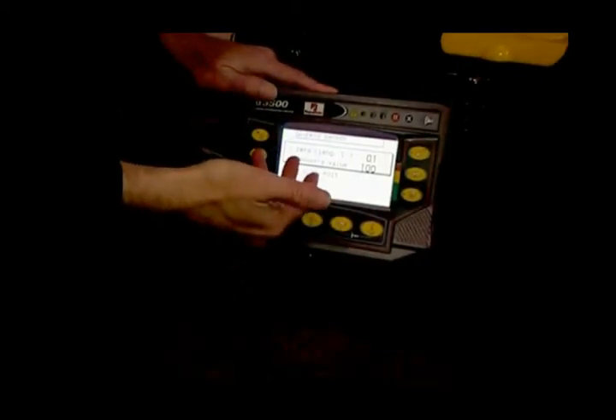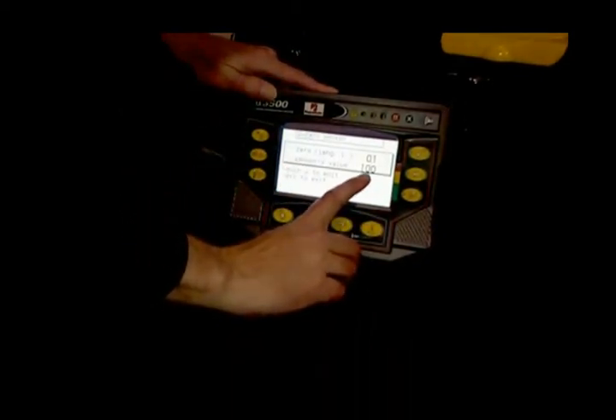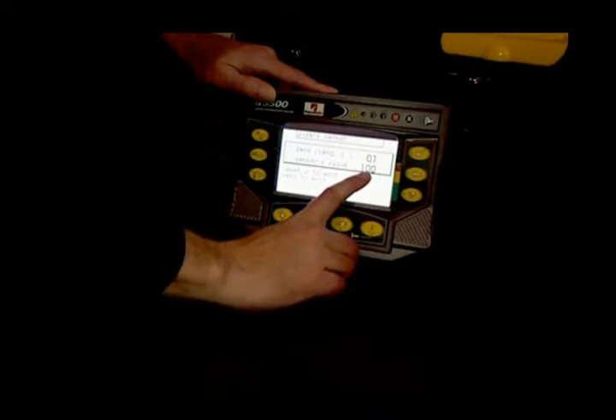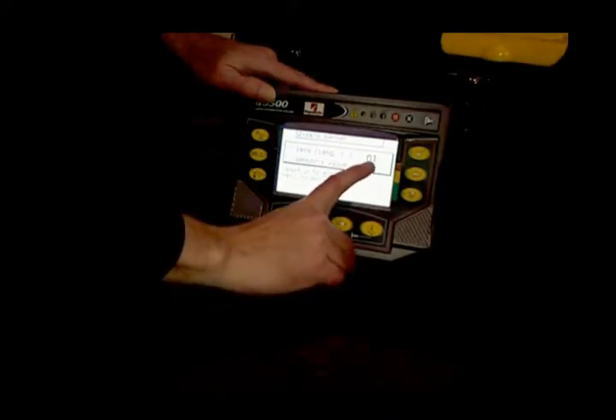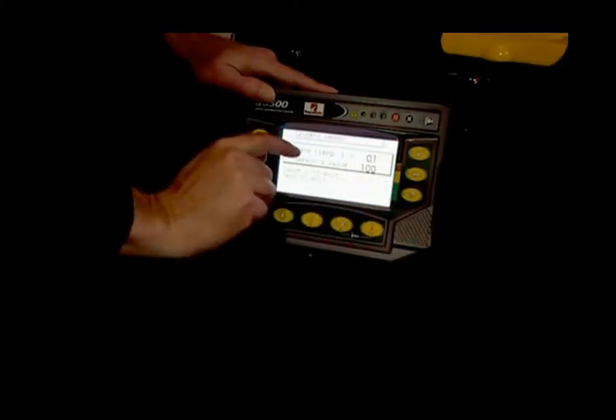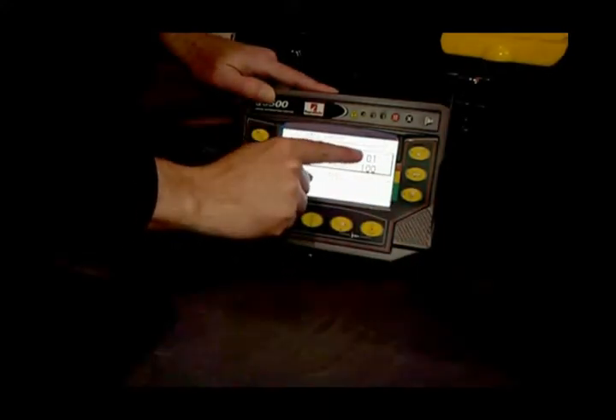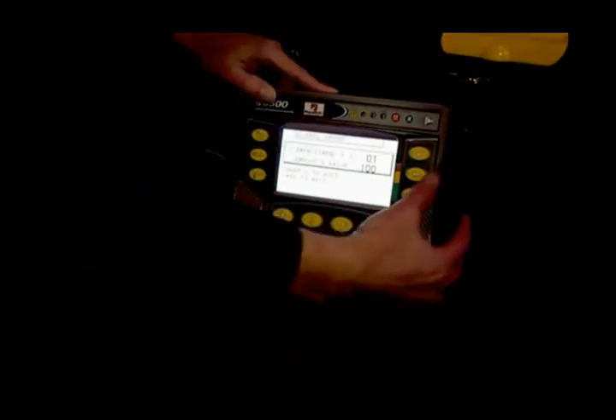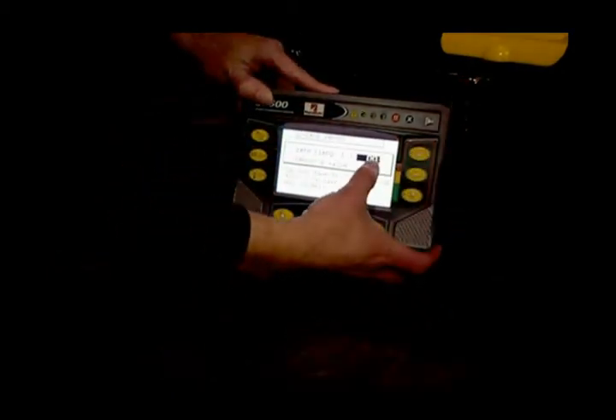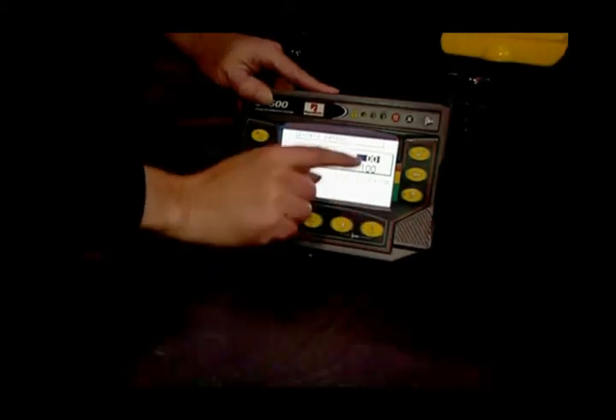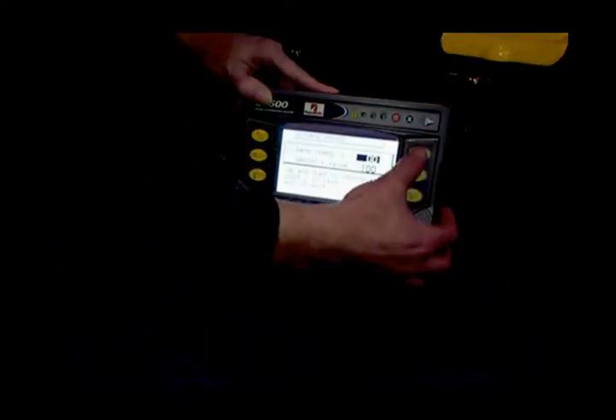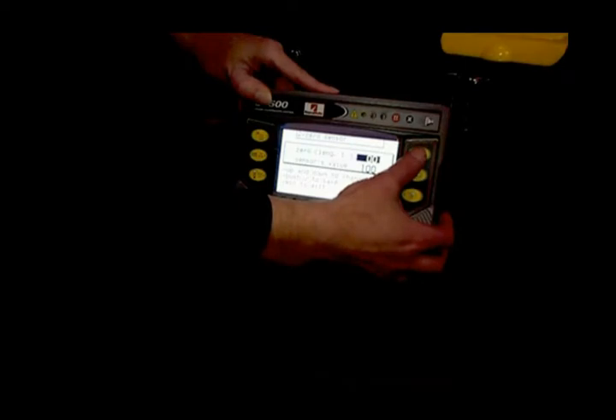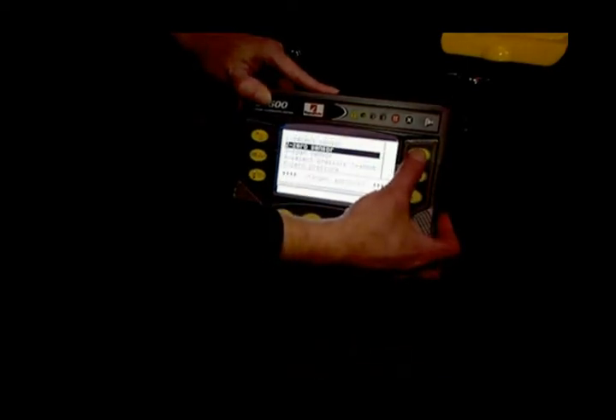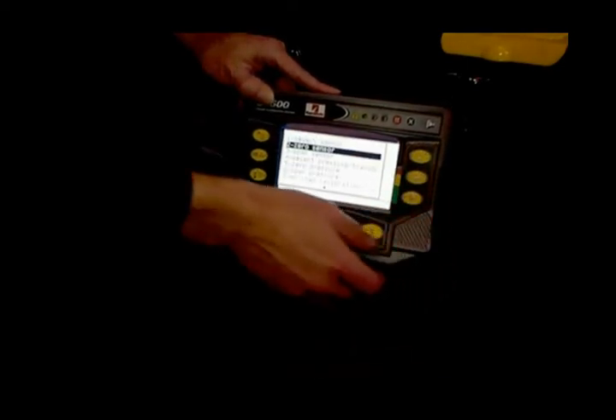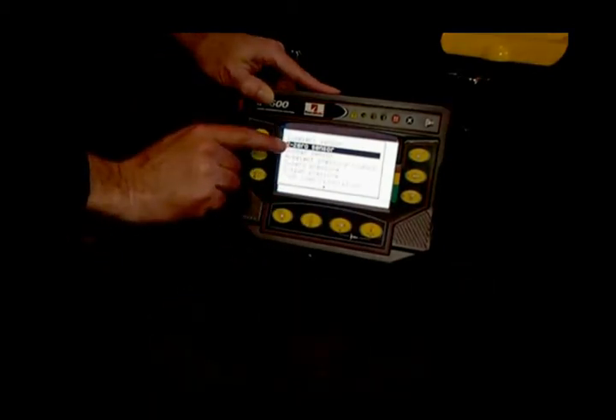So after we're in here to zero the sensor, what you're going to see is you've got a 100 for your digital value, and you've got a 0.1 in this case, or 0.0 for your actual zeroing of your length. So what you would do here is simply press the check mark to highlight it, and we want this to be at 0. So you would simply hit the check mark again, and it would save the value. And that's all you do for zeroing the sensor.